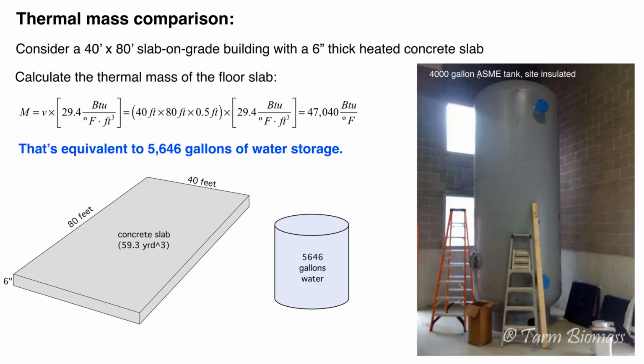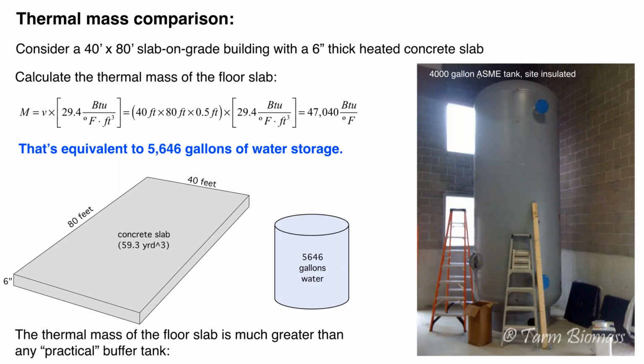And just to show you, this is what a 4,000 gallon ASME tank looks like. Typically any tank over 119 gallons, most codes are going to require ASME certification. And you can see that these tanks are made, but they're very large, very expensive. I wouldn't wager a guess on the price of that tank in today's economy. So it becomes impractical to try to match the thermal storage ability of that slab with water.